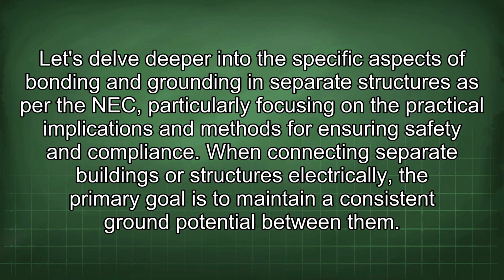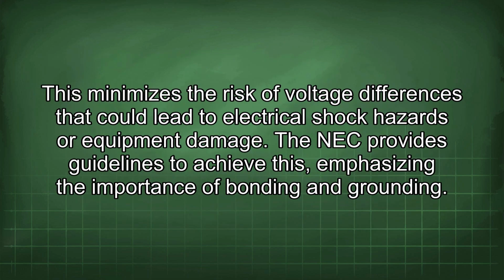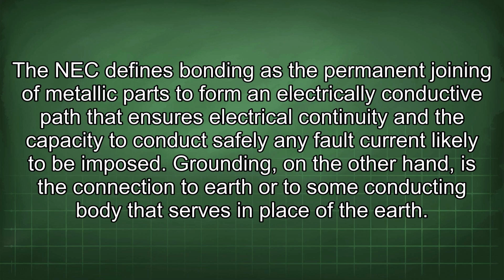Let's delve deeper into the specific aspects of bonding and grounding in separate structures as per the NEC, particularly focusing on the practical implications and methods for ensuring safety and compliance. When connecting separate buildings or structures electrically, the primary goal is to maintain a consistent ground potential between them. This minimizes the risk of voltage differences that could lead to electrical shock hazards or equipment damage. The NEC provides guidelines to achieve this, emphasizing the importance of bonding and grounding. The NEC defines bonding as the permanent joining of metallic parts to form an electrically conductive path that ensures electrical continuity and the capacity to conduct safely any fault current likely to be imposed.